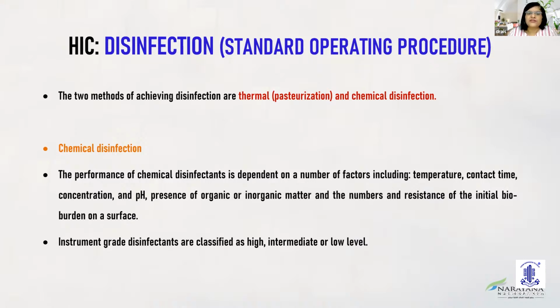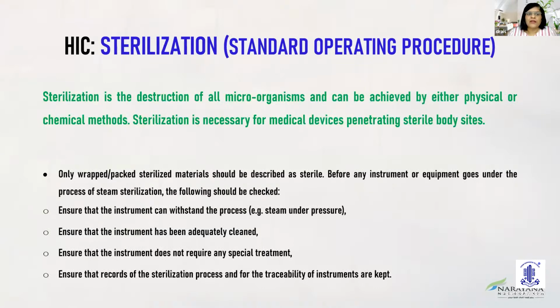Chemical disinfection is dependent on a number of factors including temperature, contact time, concentration, pH, presence of organic or inorganic matter, and the number and resistance of the initial bioburden on a surface. Instrument-grade disinfectants are classified as high, intermediate, or low level, and accordingly, chemical disinfection should be taken into consideration. Now, sterilization, as we know, is the destruction of all microorganisms, and can be achieved by either physical or chemical methods. Sterilization is necessary for medical devices penetrating sterile body sites.